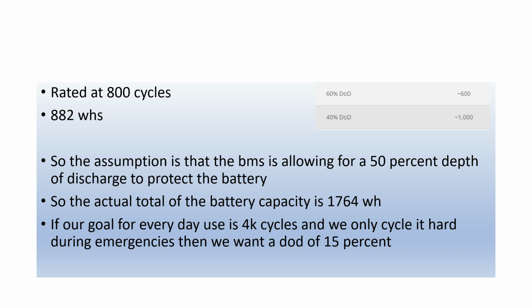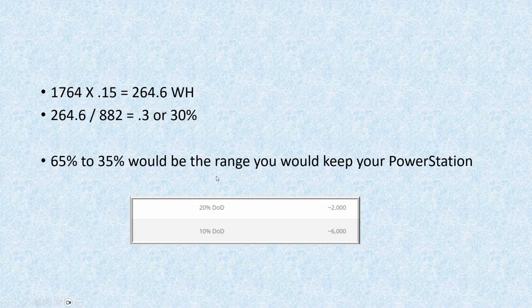So if we wanted to extend it to 4,000 cycles, we'd need about a 15% depth of discharge. As shown in the chart, roughly 15% depth of discharge gives you around 4,000 cycles.